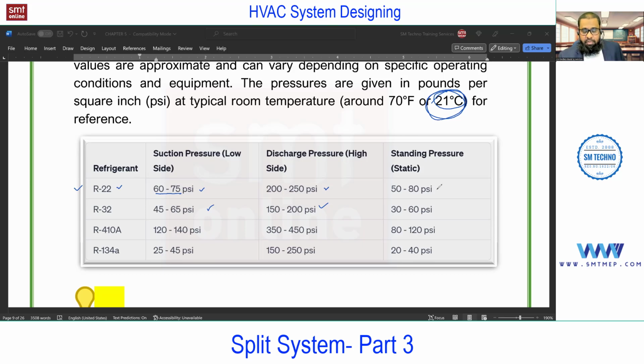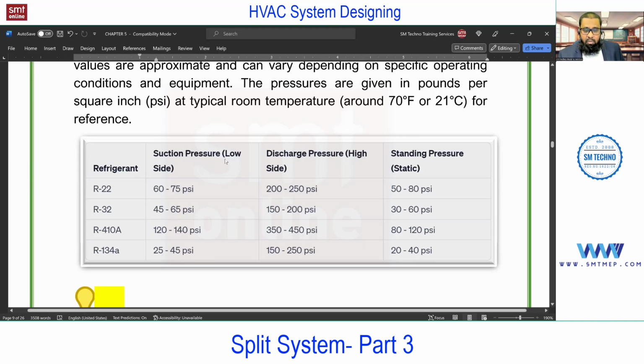Standing pressure means the pressure at the low side when the machine is not running, and all this pressure is at this temperature, 21 degrees centigrade, standard from a learning point of view. So remember, this pressure rating will vary based on the ambient temperature and also based on the refrigerant. So you can relate this.